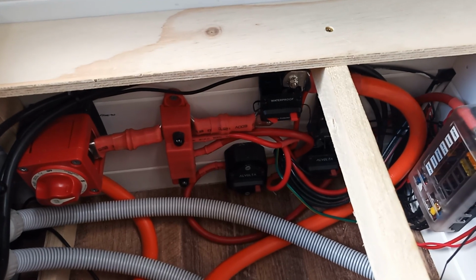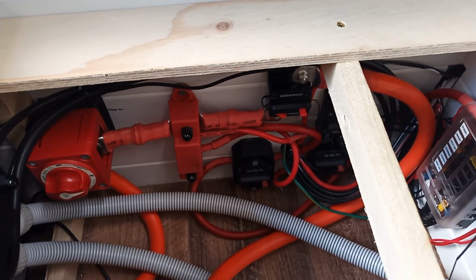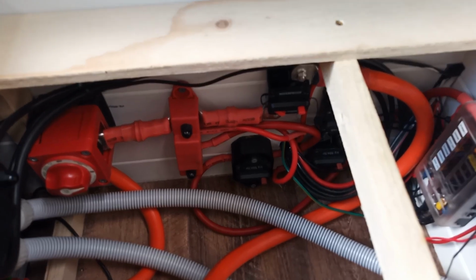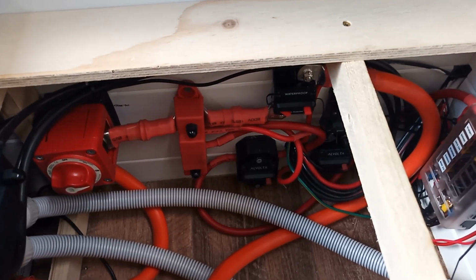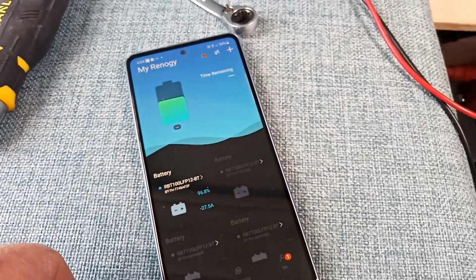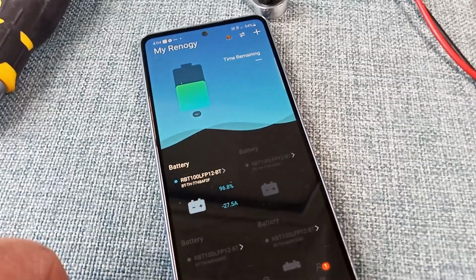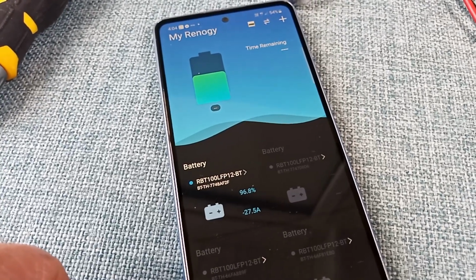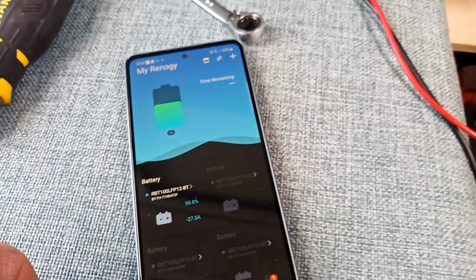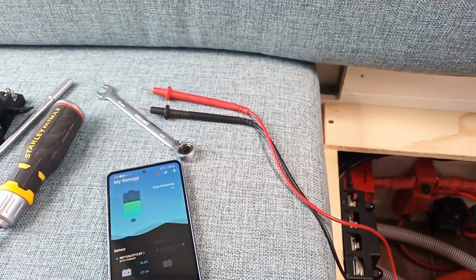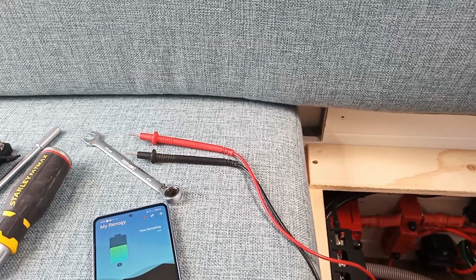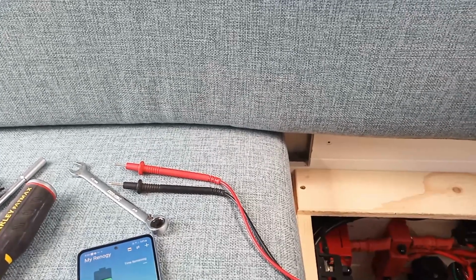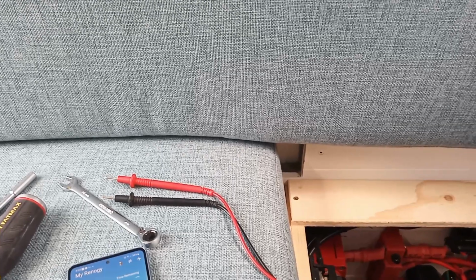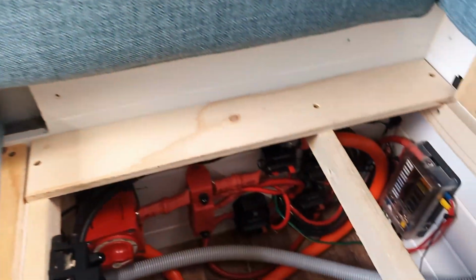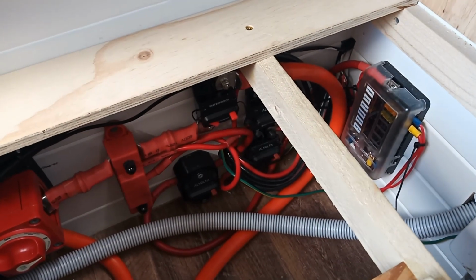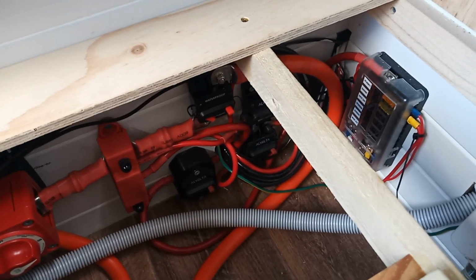Well, the plot thickens. The new one just tripped off, which the old one wasn't doing. I wouldn't have thought it was doing 300 amps. So it's just tripped off again. As you can see, this battery was reporting 27.5 amps at the time. Assuming all the batteries were doing roughly equal work, 5 batteries at say 30 amps each is 150 amps, meaning this circuit breaker is tripping at about half of what the current should be.